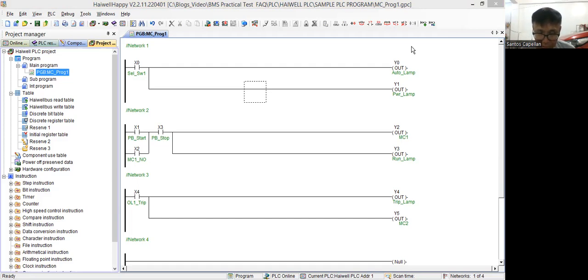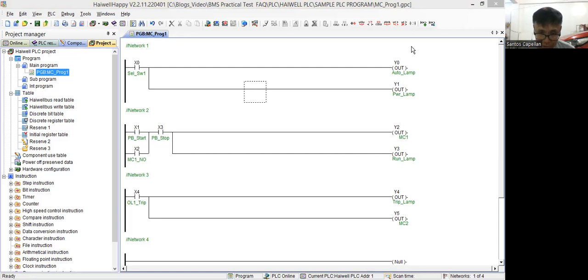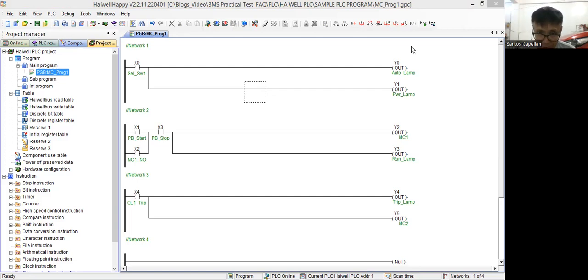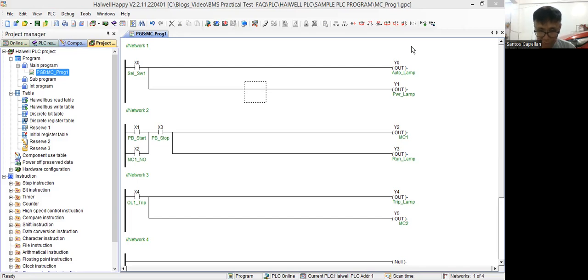I will go back to the plan, but I'm just going to show you how this PLC is controlling this simple motor control. As you can see based on the program, if I put it in automatic, then two of the relays will be activated to power up or to display the proper indication in the motor control, like the power on and the auto position. Then you can see also in the digital inputs and output, the terminals, which are in on or high condition. X1 and X2, X3, Y0 and Y1. Now, this time you can just try to start the fan by pushing the push button here.